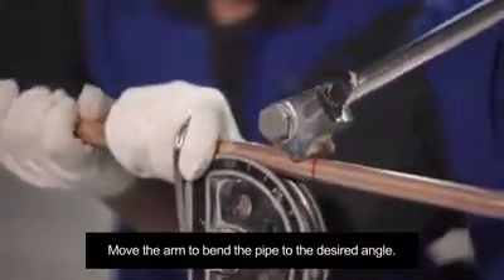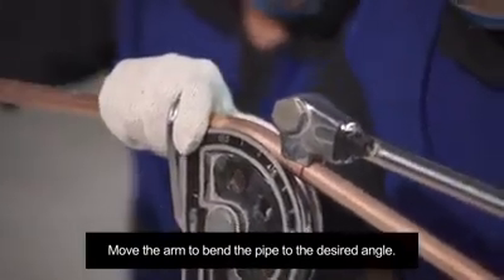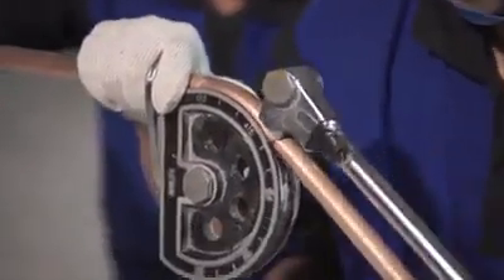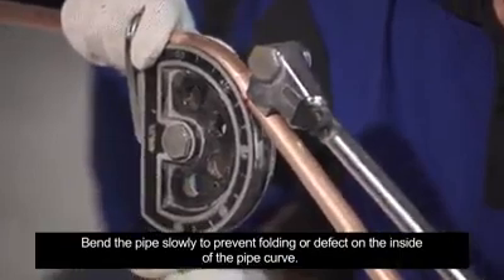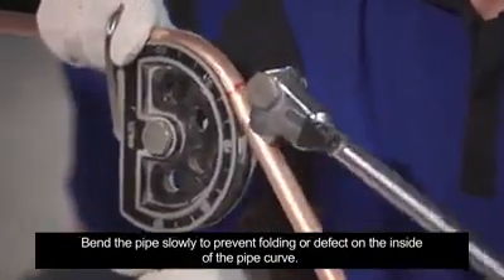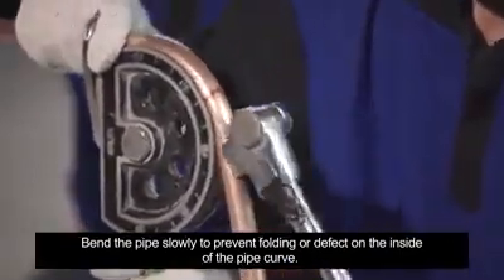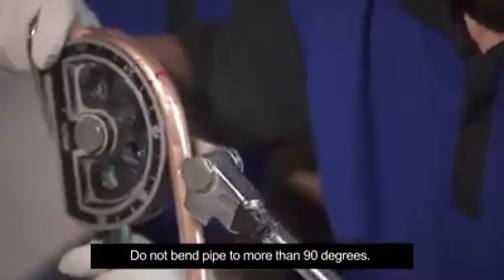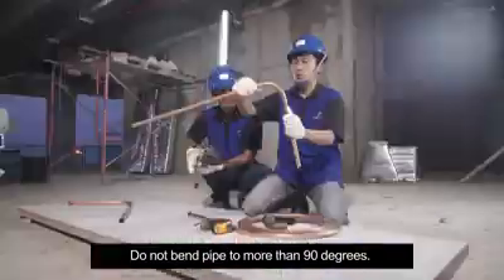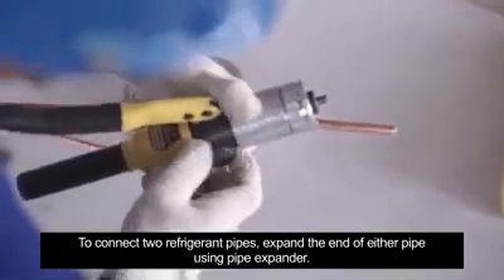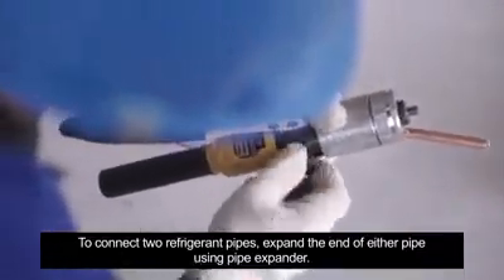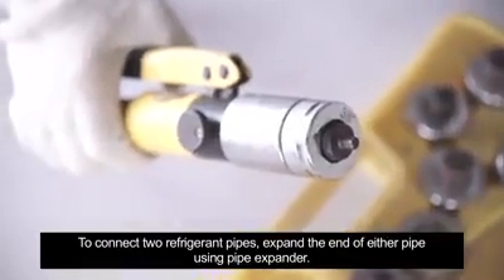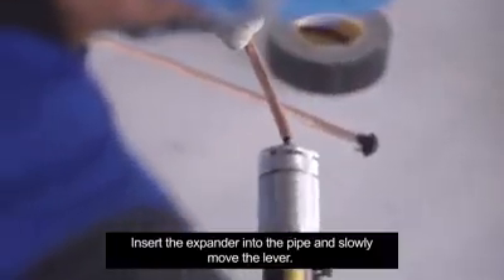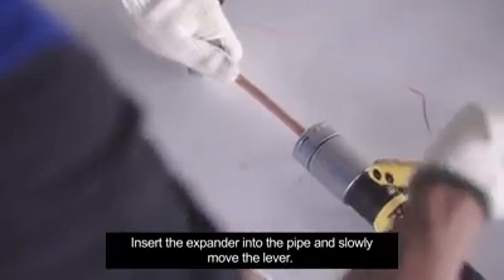Move the arm to bend the pipe to the desired angle. Bend the pipe slowly to prevent folding or defect on the inside of the pipe curve. Do not bend pipe to more than 90 degrees. To connect two refrigerant pipes, expand the end of either pipe using pipe expander. Insert the expander into the pipe and slowly move the lever.